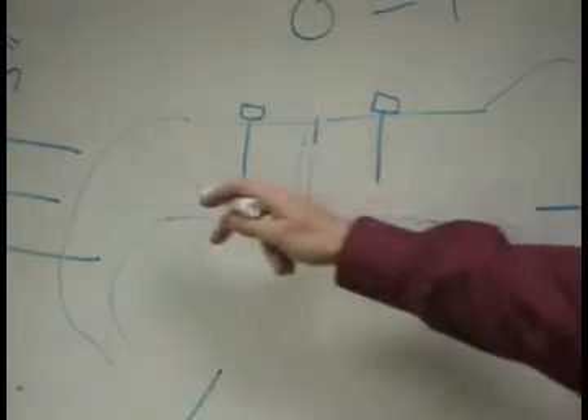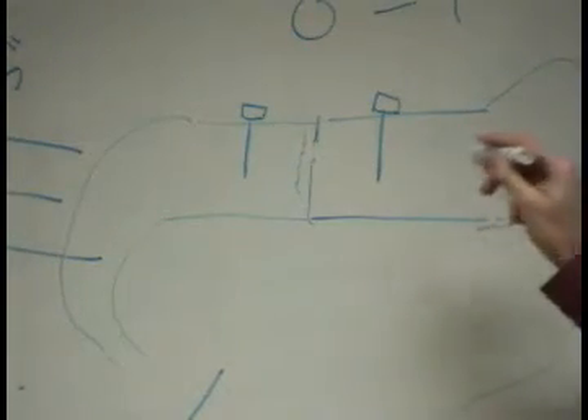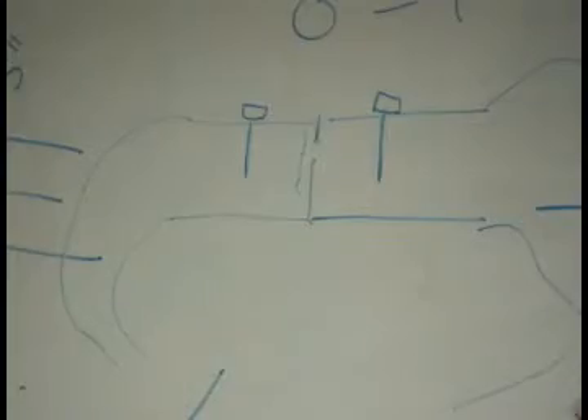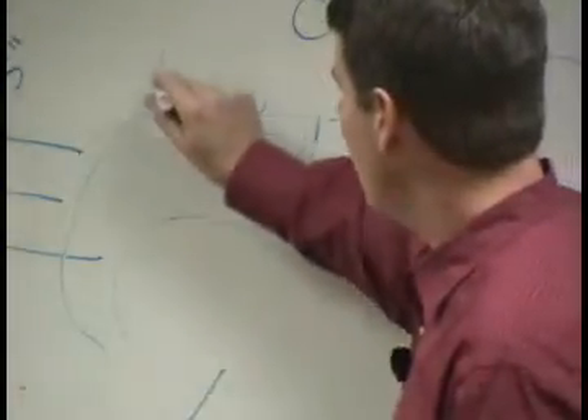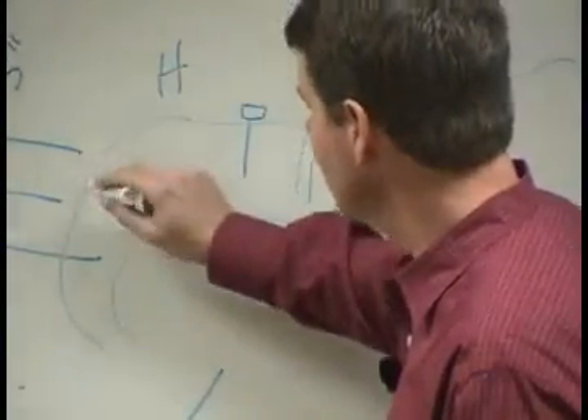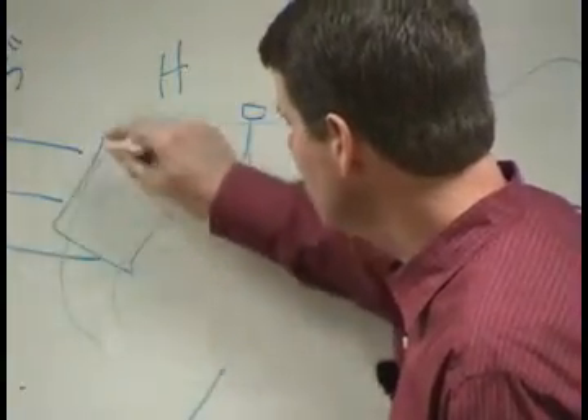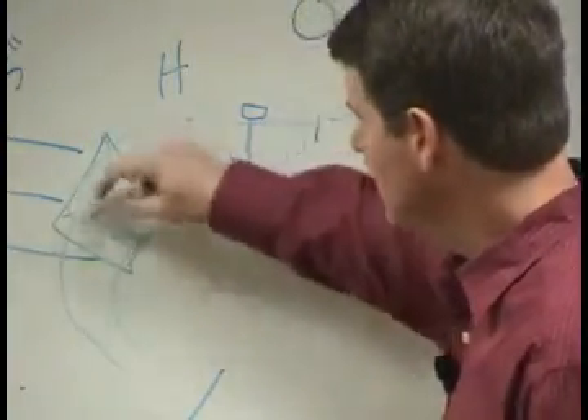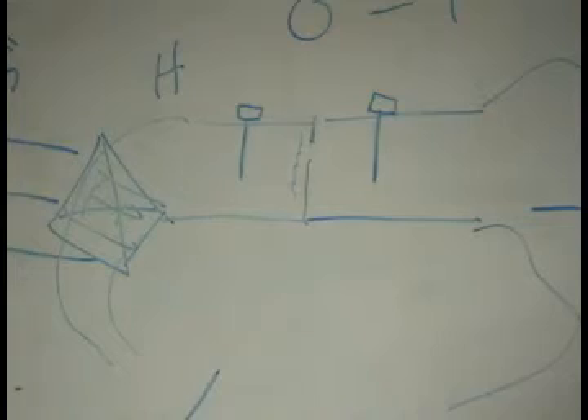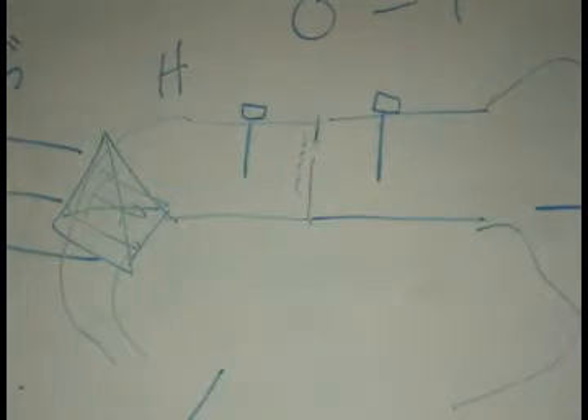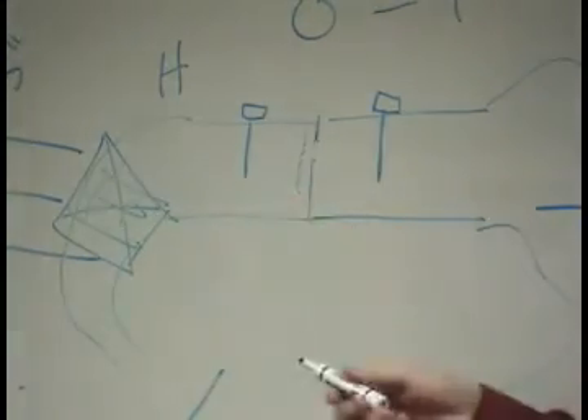So we actually have air flowing through that sensor, which means on the high side, we've got a filter to keep any of the lint and crud out of that orifice and out of that sensor, because otherwise, you know what the inside of the ducts look like. They just fill up with dirt over the years. So you got to have that filter in there.